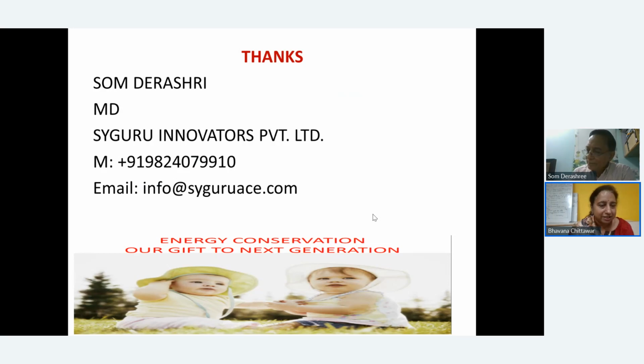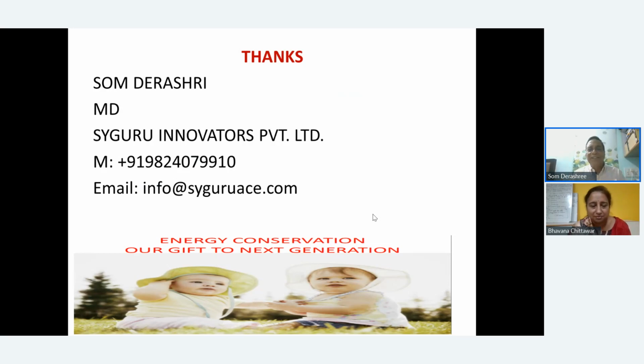Mr. Balkrishna has another question. During pump selection, should the point be slightly on the right side of the best efficiency point? It could be right or left, because on both sides it's immaterial. I said 80 to 110% is okay. You can't be exactly on that, because once you start operating, you will find a lot of things have changed from what you contemplated during the design stage, and you have to fine tune. Maybe you change impellers, or you do what we have done. It was an already designed running plant where we did some retrofits to improve the system.